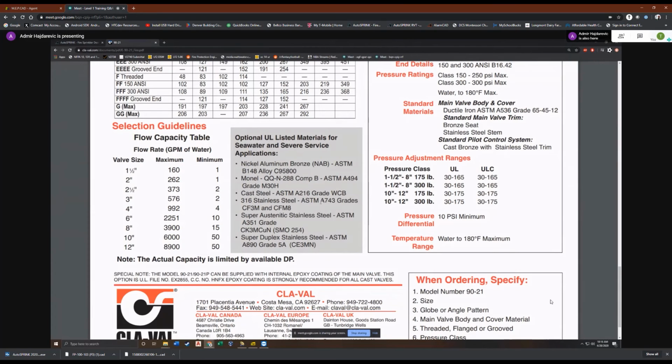Generally, with that type of approach, you're going to have a huge safety factor. Yeah, which is what I always have. We have a 70 plus pound safety factor. Could you squeeze the pipe down? Yeah, sure you could, but then you have to tell the fitters to be careful on every extra elbow they add and whatnot.